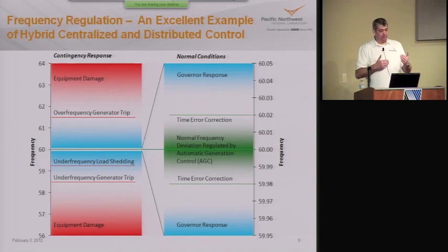And generally, this varies a lot by the type of turbine. You know, nuclear plants and coal plants are different than hydro plants, but they all have to be protected against overspeed or underspeed. And generally, that's in the 1 to 2 hertz range. So, from high speed of 61 to 62 hertz, kind of in that range, you'd be starting to trip generation. Similarly for low speed.